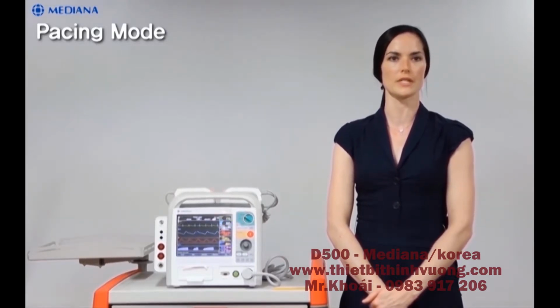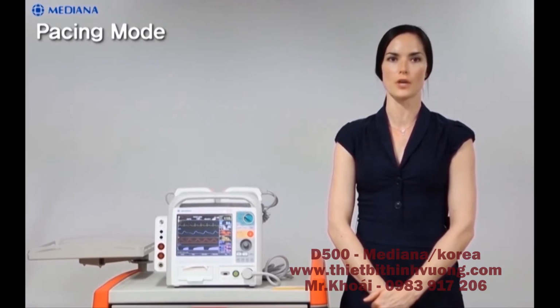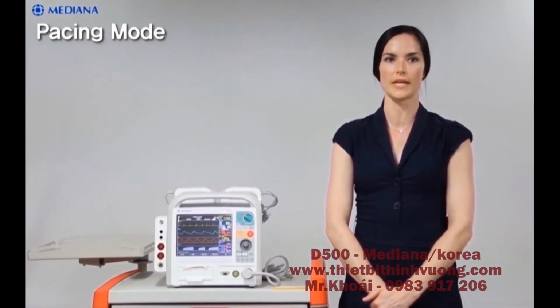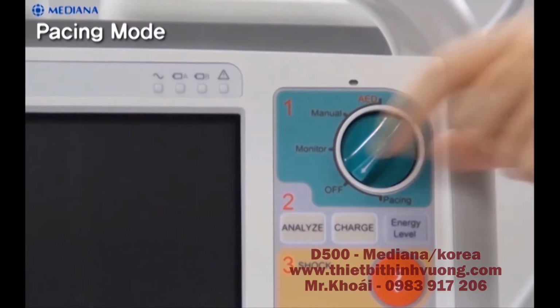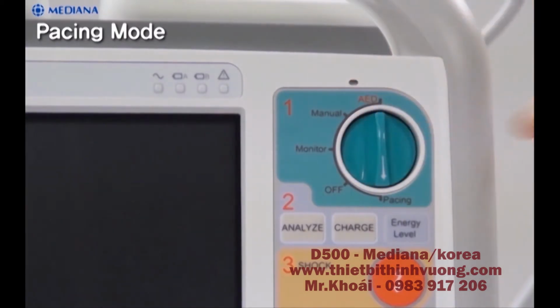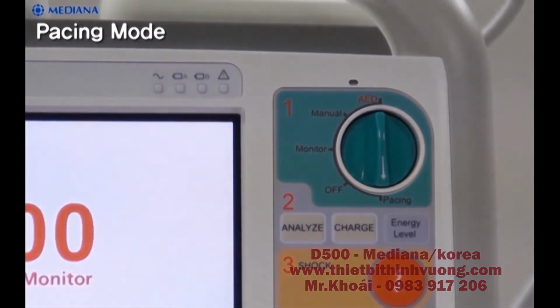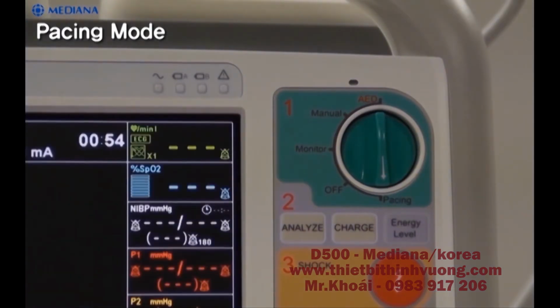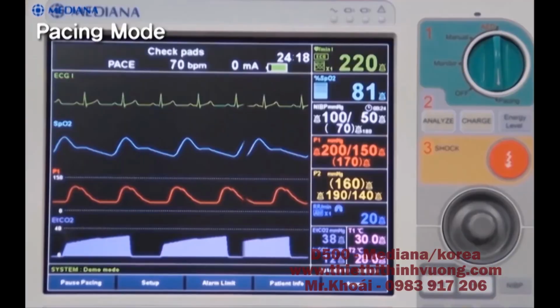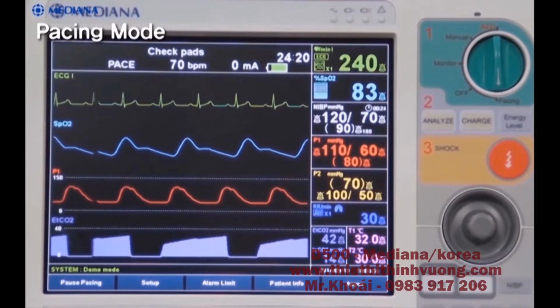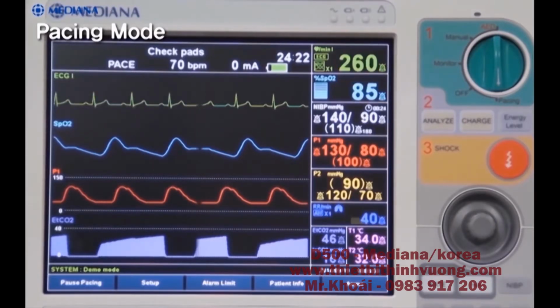In sync mode, the D500 only delivers pacing pulses when the patient's heart rate is lower than the selected pacing rate. In async mode, the D500 delivers pace pulses at the selected rate. Let's see how to use the pacing mode. First, select the pacing mode of the D500 by rotating the mode select knob.